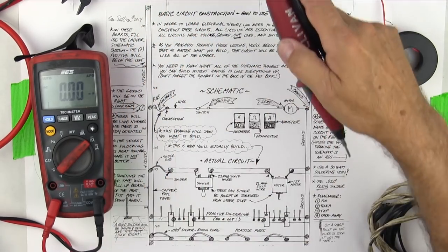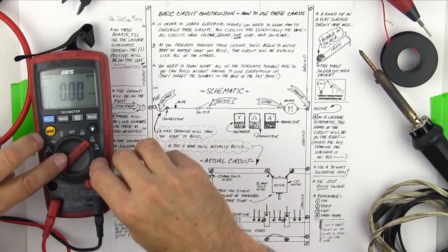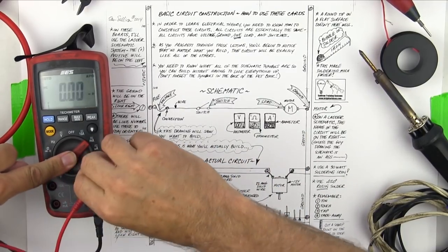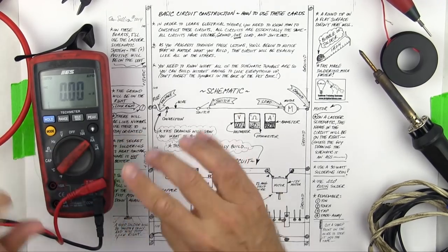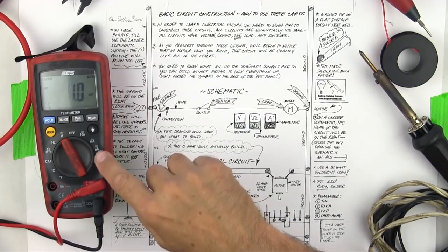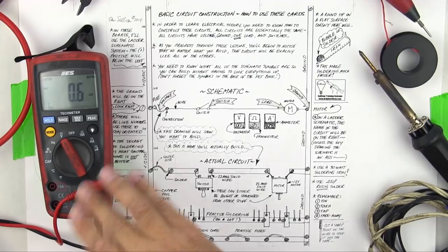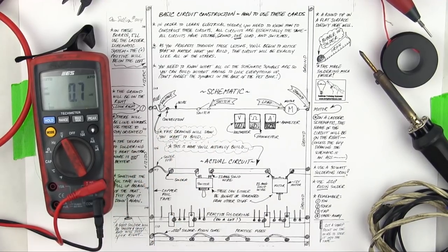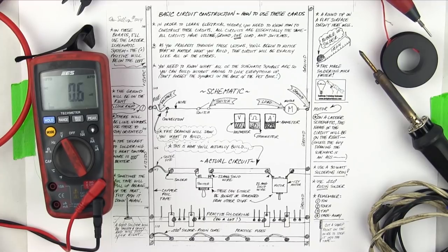That's how I anticipate you guys will be using the amp meter throughout this process, because I want you to become comfortable with all the different meters and how they work. The big caution is if you forget to move this back and you decide to start reading voltage again, then you're probably going to blow the fuse in your meter. The only thing the fuse in the meter protects is the amp meter functions, so it'll still work on volts and ohms, but it won't work on amps. You need to be careful about that, and I can guarantee you that at least once in this process you are probably going to blow your fuse.